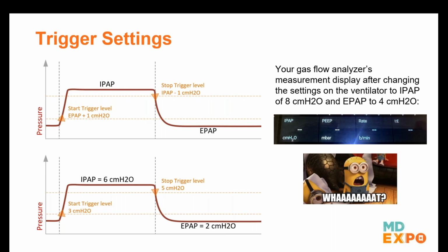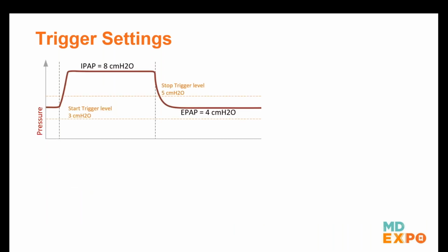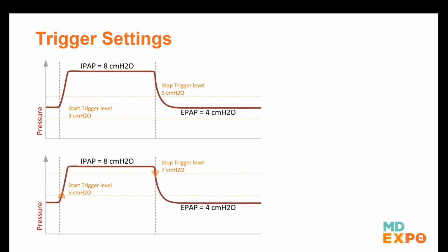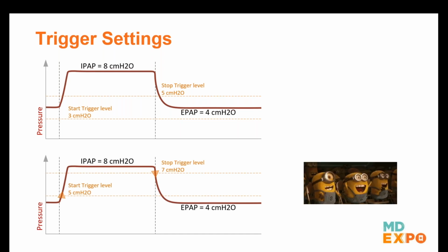Yeah, it's not triggering anymore, right? If we have a look at the updated graphics here, our start trigger level was at 3, and now our pressure is never going to go below 4 anymore because we have the setting now on a higher level, right? So to resolve this, we'll have to amend our trigger settings to the new settings on the ventilator so that the device can trigger again and measure the breath-based parameters.